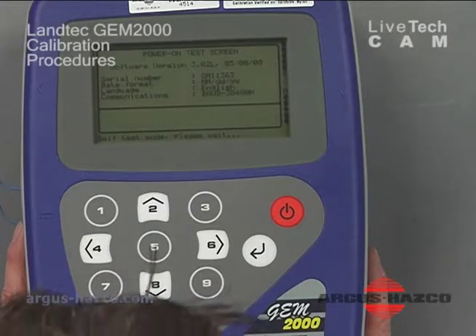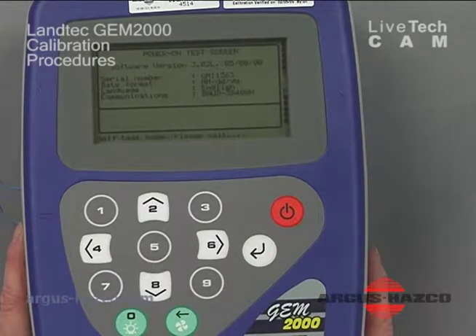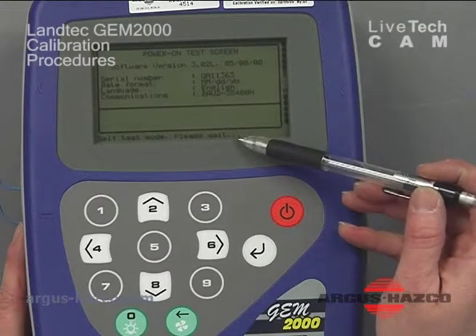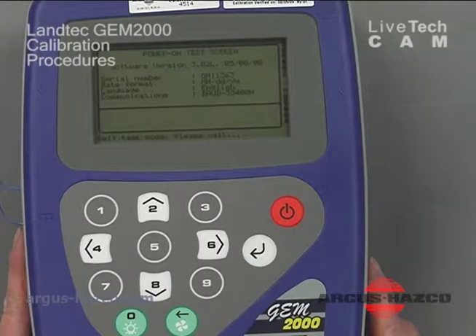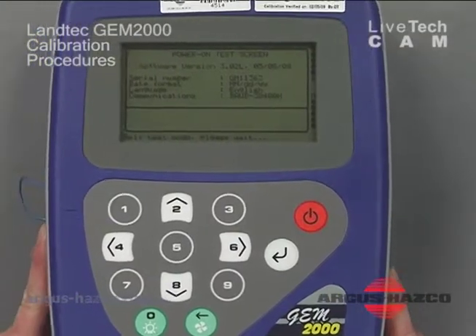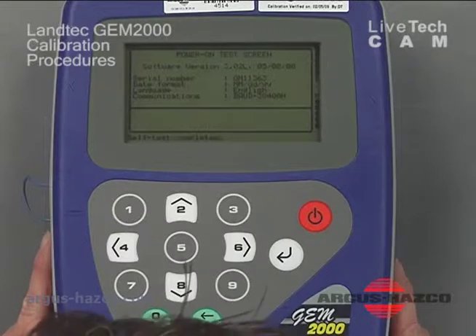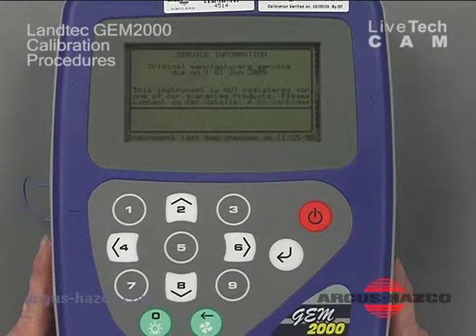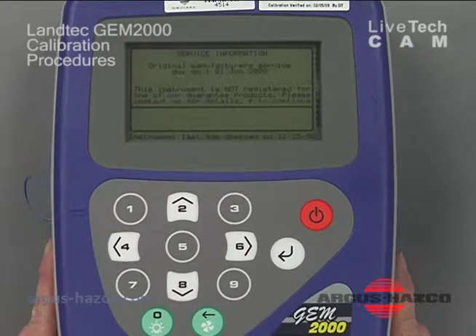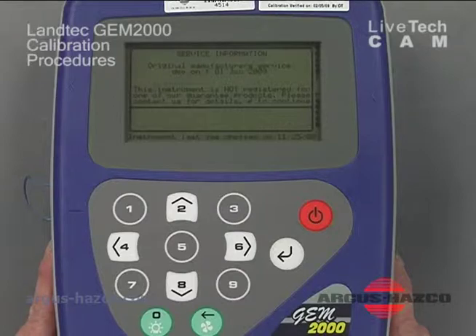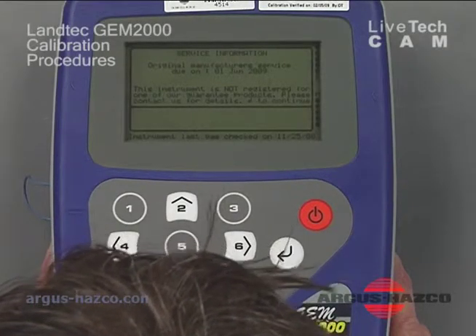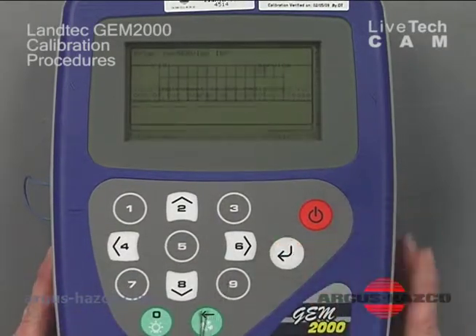And once it tests all of its different functions, testing the pump. It's still in its self-test mode. Please wait. Now the self-test has completed. Instrument gives us a service information screen. And then after the service information screen, we go ahead and hit enter to continue.